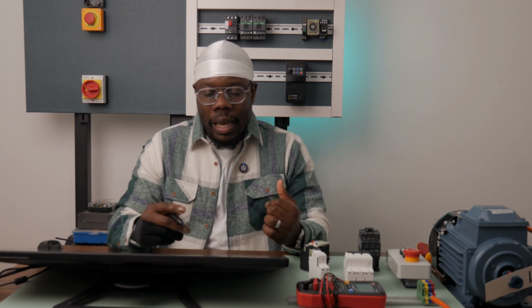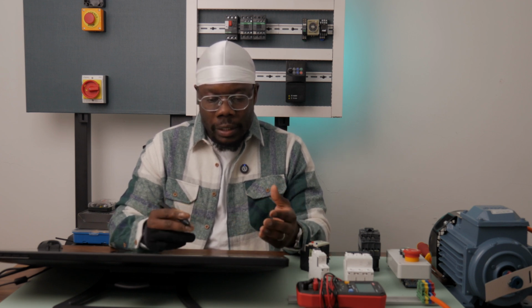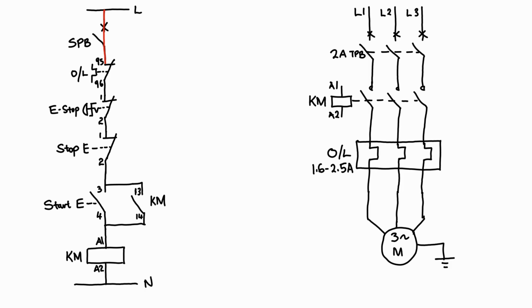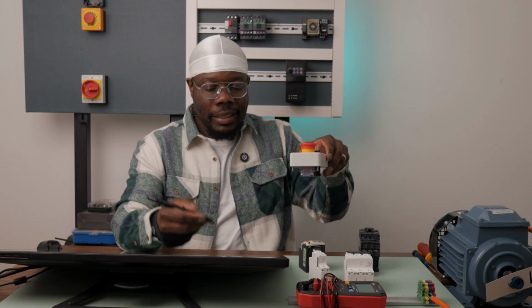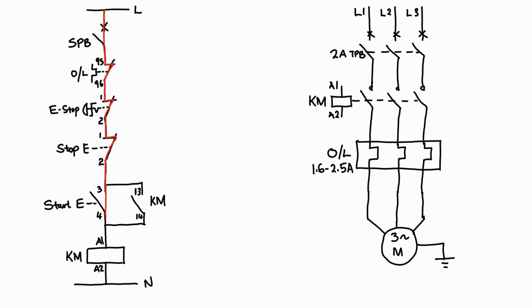I'm just going to explain briefly how the control circuit works. After you've wired up your circuit, obviously you switch on your control circuit breaker. When you press the start push button here, this contact is going to close and current is going to flow from your supply through the normally closed contacts on your overload relay. They are closed, so they will allow current to pass through. The stop push button as well is normally closed, so it will allow current to flow through its contacts. As current flows through the start push button while our finger is pressed on it, it will power up the contactor coil at A1 and A2. It doesn't matter where you connect your live or neutral, current will flow through and power up this contactor.